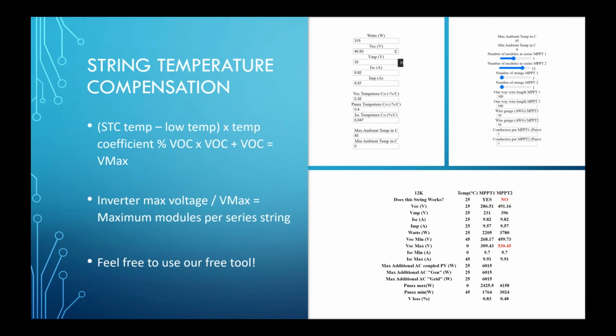Again, the voltage open circuit is a stringing concern for any inverter. You have to watch something. We have 3 things: 500 volts open circuit for your panels when you're stringing them, 48 volt for your battery, and either a 240 or 208 volt generator. Those are the basic electrical requirements. But other than that, you can use any battery solution, any inverter solution, and any solar panel solution. This particular tool is on our website, and it's to help installers with stringing solar panels to our inverter.